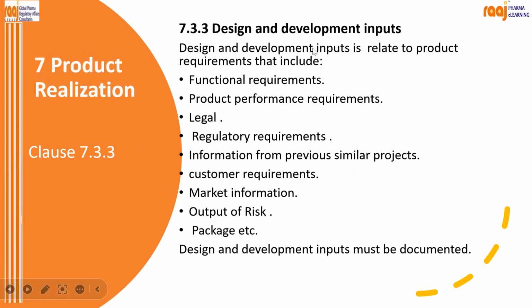Then design input. What will be the input? Your functional requirements, product performance requirements, legal requirements, regulatory requirements, information from previous similar projects, customer requirements, market information, all that is covered here. Here you get the predicate device also, right? You see the predicate device, what its functionality is, and all those things will be part of your design and development inputs.